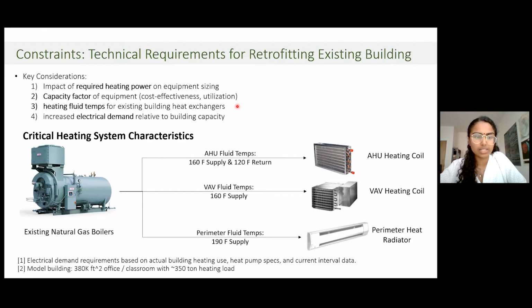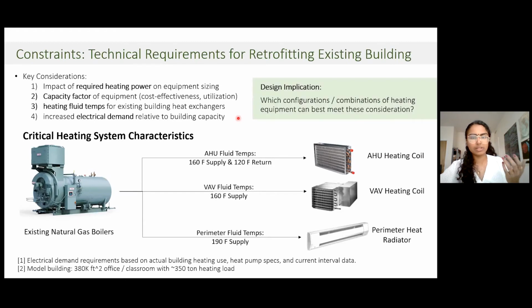We've looked at the heating fluid temperatures that we can expect or that we require for existing building heating exchangers, and what we need throughout the heating season. We can also look at the impact of increased electrical demand on the electrical supply that we have on the building, and whether we might need to expand that to accommodate an electrified heating system. All of these key considerations come into the following question, which is which configurations and combinations of heating equipment can best meet the technical requirements for retrofitting an existing building.